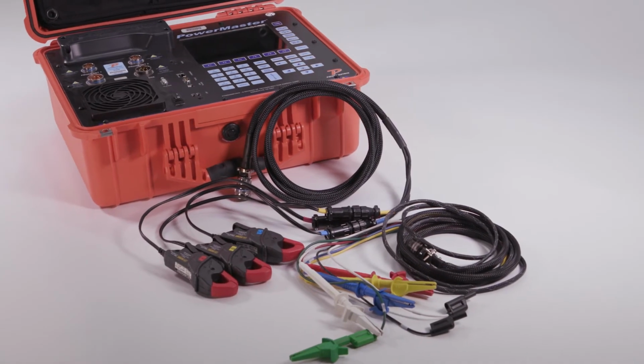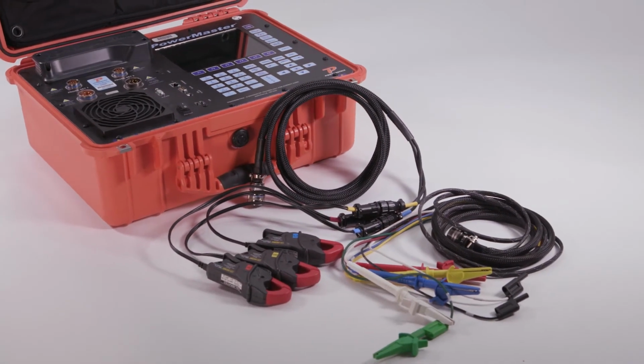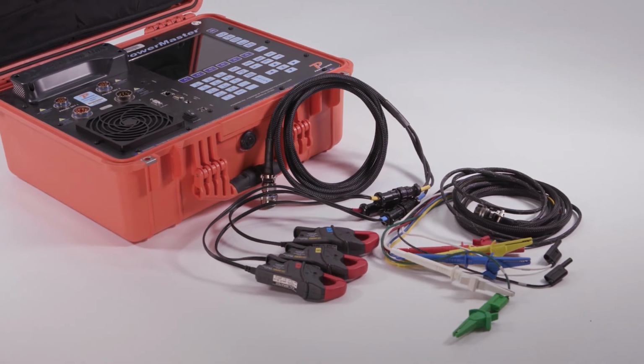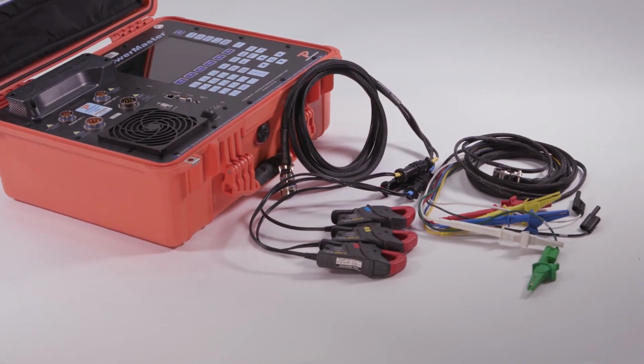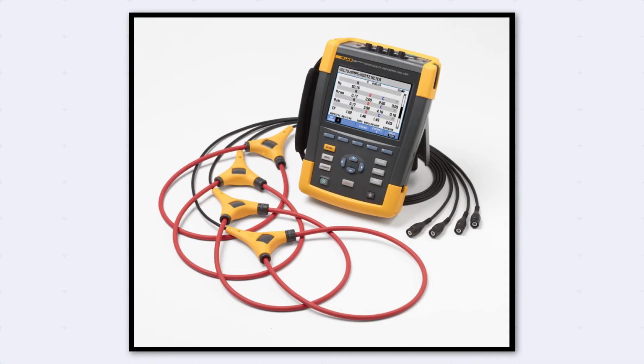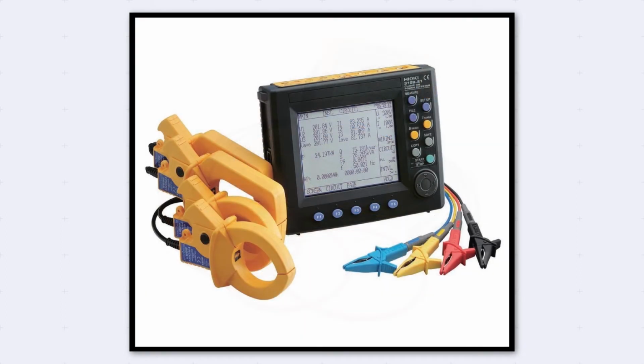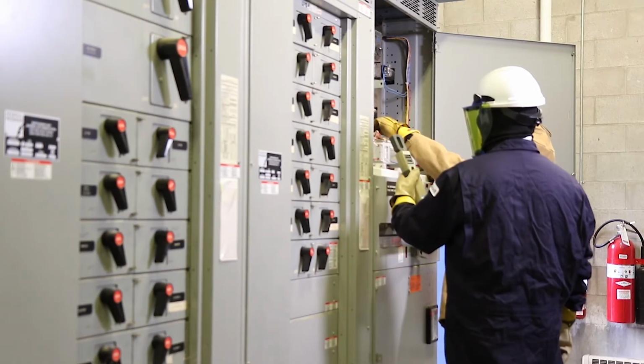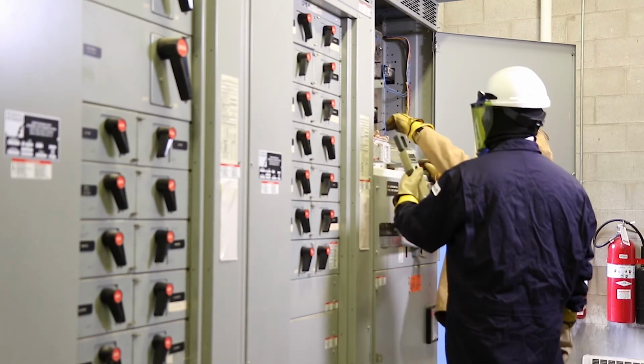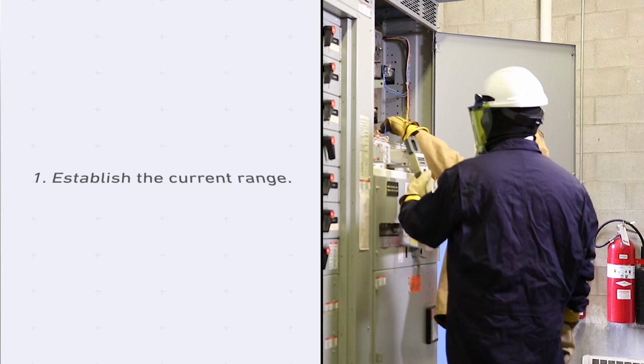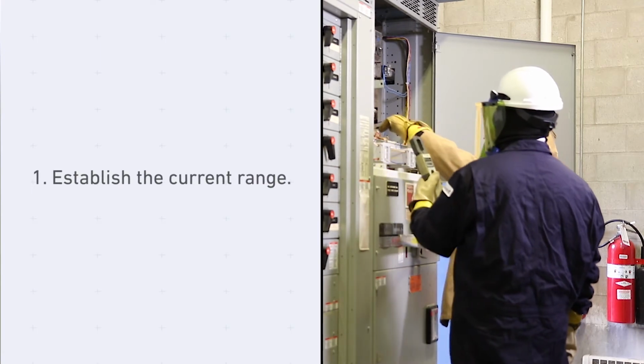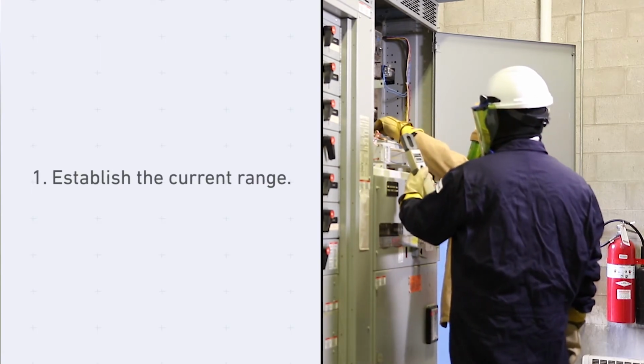Most analyzers used by Measurement Canada inspectors now permit simultaneous measurement of primary and secondary currents, and some display the ratio directly. With the Fluke and Hioki analyzers, you have to do the calculation, but both primary and secondary currents can be measured and displayed simultaneously. The following is the procedure for determining current transformation ratios. 1. Establish the current range in which you are expecting to measure for the service.